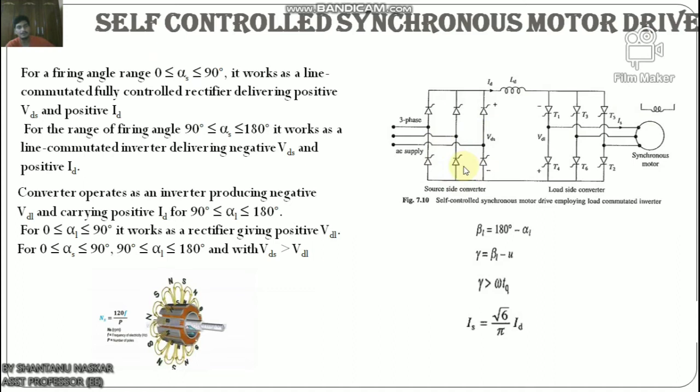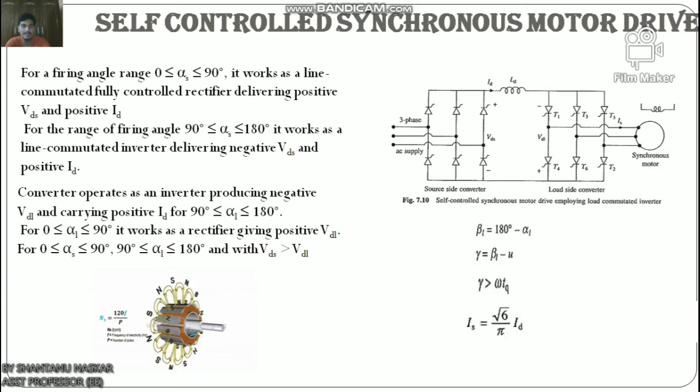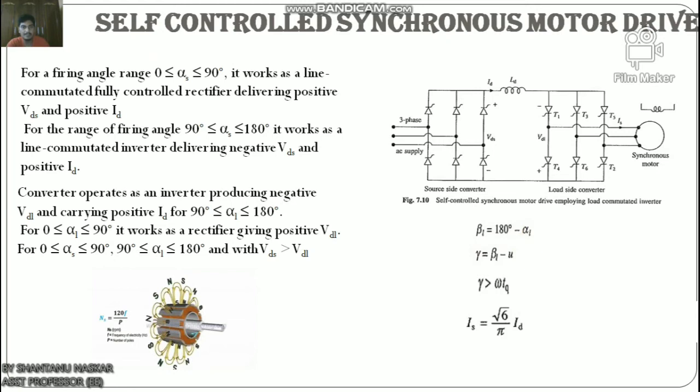The magnitude of torque depends on Vds and Vdl. Speed can be changed by controlling the line-side converter firing angles. When working as an inverter, the firing angle must be less than 180° to account for commutation overlap and thyristor turn-off time. It is common to define the commutation lead angle for the load-side converter as β1 = 180° − α1.